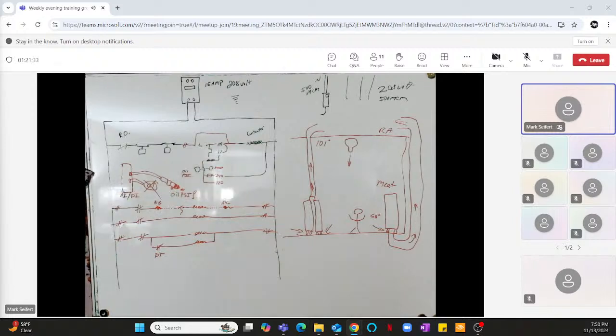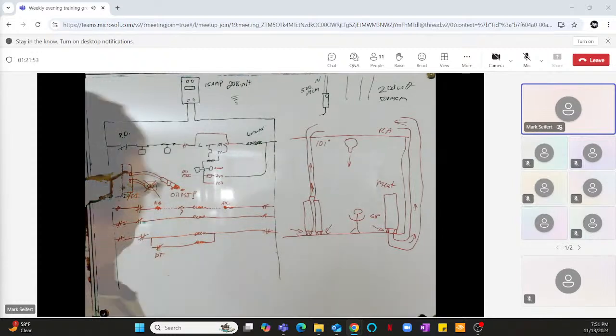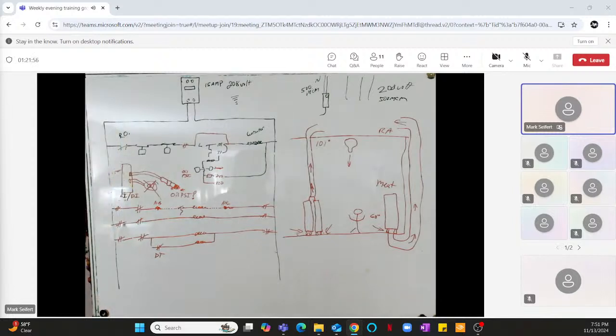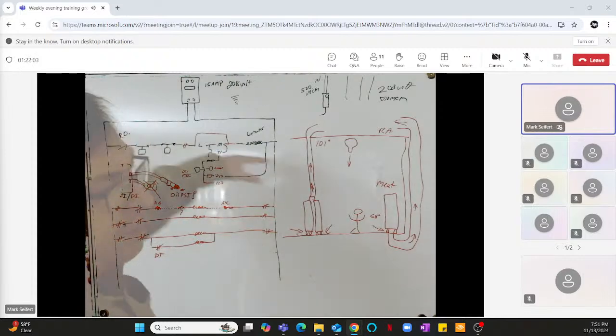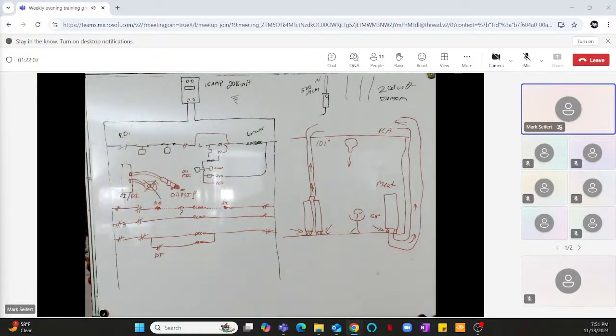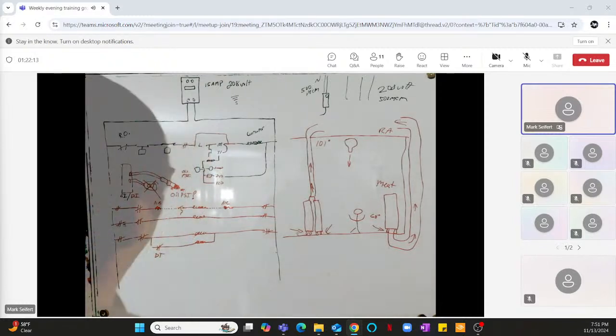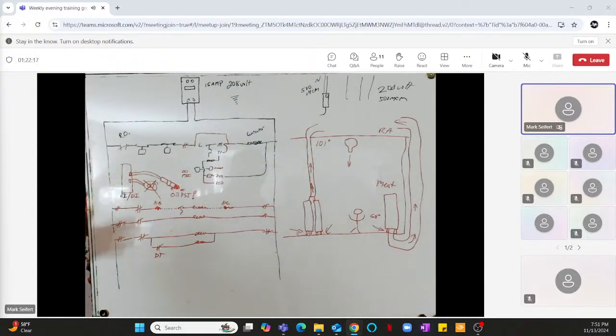There is a scenario where it's got no oil pressure and it still runs. Like, I'm not sure on a lost board if that'll do it. If it shows lost on an AI/DI board, will that do it? I'm not sure. I haven't run across that. It might. The E2s are pretty smart. It might say, hey, I got a lost board. I'm not going to chance it. I'm not going to run the compressor. So those are all scenarios you've got to be running through your head. Like, okay, what's going on here?